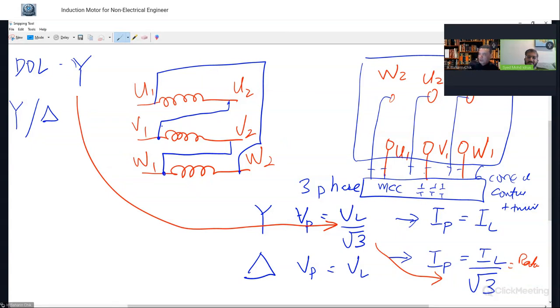It is more on electronics, power electronics. Because just now we tried star delta and it was not possible, the voltage drop was still very high. Then we went for an auto transformer, still very high. Then the next step is we go for a soft starter. A soft starter is like a VFD too, but on the lower side. So we can set the starting current maybe at 3 times or 300% of the full load current. But for a VFD, the starting current is only 100%.